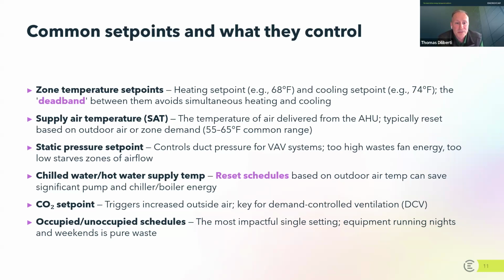Other set points are supply air temperature set points, and I'll give you a range here, maybe between 55 and 65 degrees. Static pressure set point. Again, this is going to come up a lot over the next half hour as we talk about systems and the pressure. Chill water, hot water set points. And I flagged something else here, what's called a reset schedule. This reset schedule really is a critical idea for energy management.